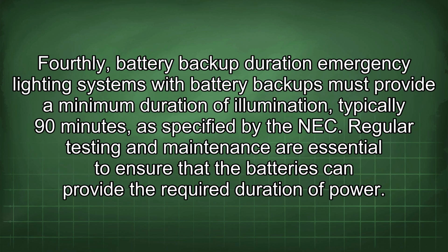Fourthly, battery backup duration. Emergency lighting systems with battery backups must provide a minimum duration of illumination, typically 90 minutes, as specified by the NEC. Regular testing and maintenance are essential to ensure that the batteries can provide the required duration of power.